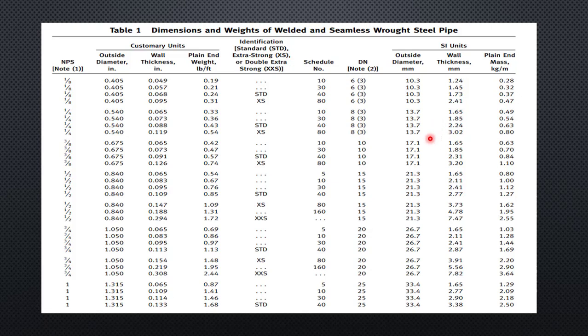For most Indians, metric standards are more convenient as we are used to them. From this standard's Table 1, you will get the size of the pipe, the OD, the wall thickness, and the weight per foot. In metric units, the same values are given in mm and weight in kg per meter. You will also get details of different wall thicknesses available for a particular pipe — for example, schedule numbers 10, 30, 40, and 80. Each schedule number has a different thickness, and you also have Standard and Extra Strong (XS and XXS) designations.